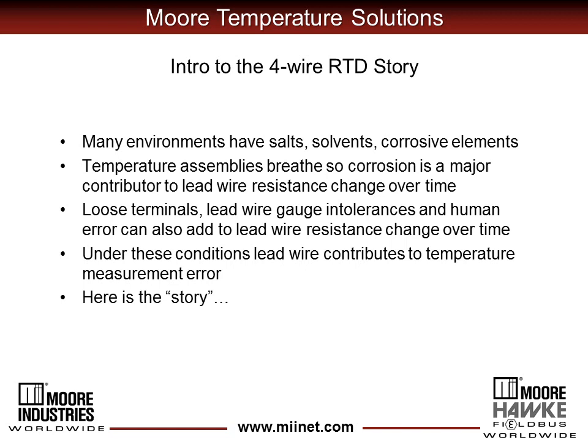If you've not studied this topic, you might be lulled into thinking that RTD extension wire, which is copper, does not introduce error into the RTD measurement. But RTDs are resistors and copper wire is resistance. So in fact, copper wire can cause significant error in an RTD measurement. There are many contaminants in the typical process plant that cause corrosion, and that corrosion changes resistance. Resistance change in lead wire contributes to error. To eliminate lead wire error, the solution is to use four-wire RTDs.